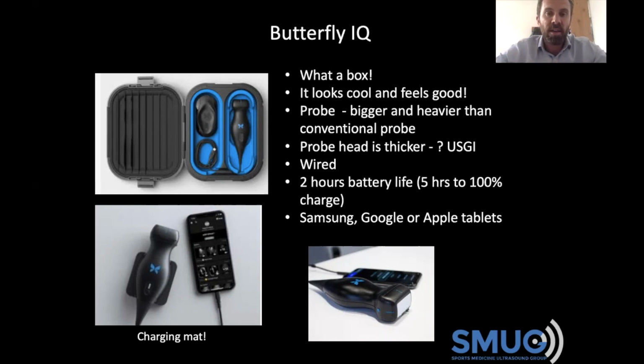And from my understanding, the reason that you have to have the battery inside is that this is Apple compatible, and it is literally, from my understanding, the only handheld device that is Apple compatible at the moment, and you can't take the battery out of an Apple tablet or an Apple phone. Whereas the Philips Lumify, as some of you will know, is plugged in and it's a very light probe. You don't need to have the battery in the probe, because with Samsung devices, I believe, and with Android devices, you can actually take the power from the battery within the tablet or the phone. So although the Butterfly is wired, it is a bit of a heavier probe because the battery is inside it as well. Now, I did carry out a few guided injections just on meat specimens.